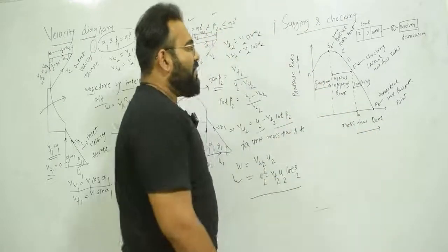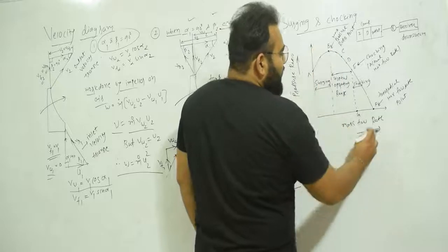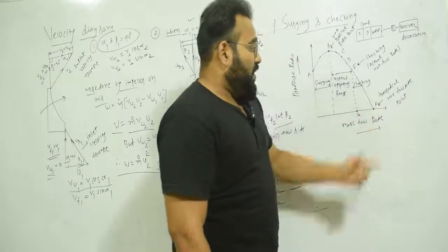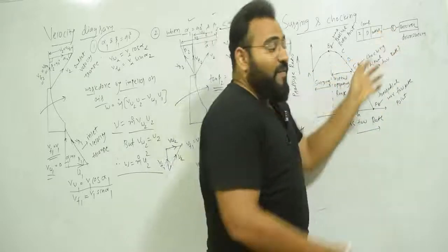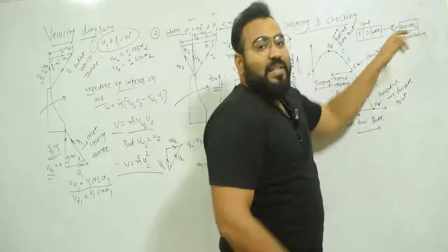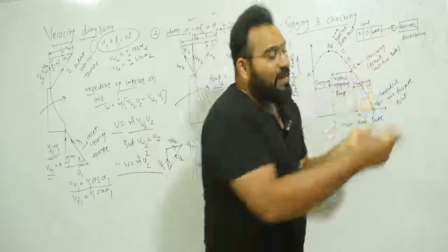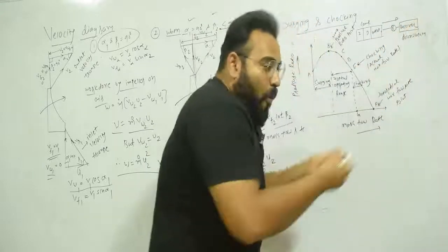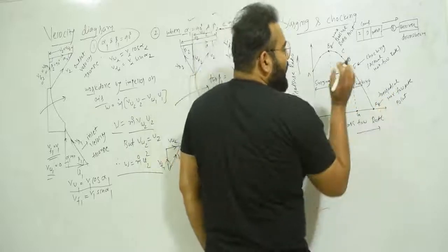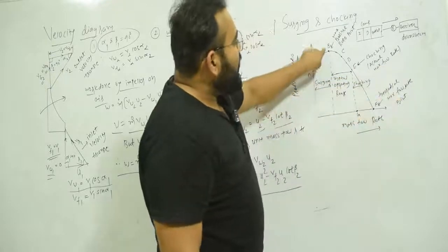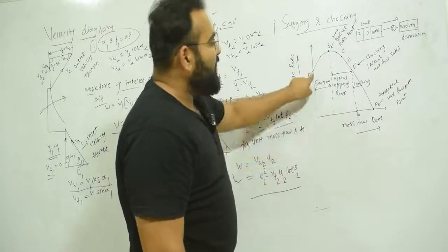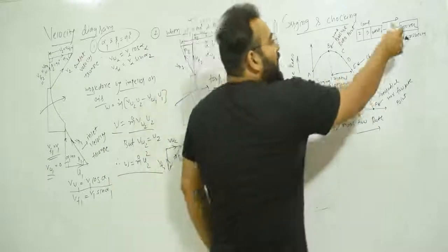I have drawn a diagram with mass flow rate on the x-axis and pressure ratio on the y-axis. Point F is the theoretical maximum flow rate point — when the control valve is fully open. Point E is the actual maximum flow rate point. Point P is the maximum pressure ratio point. Point A is where mass flow rate is zero — the control valve is fully closed. Even at point A there is some pressure ratio because air is trapped in the impeller blades.